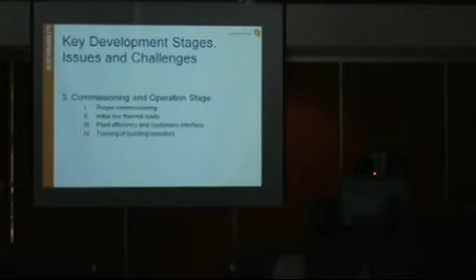So we initially suffered from a low thermal load, because we invested ahead of time. We put in too much boiler and chiller capacity, but the occupants moving in were much slower than we expected. So plant efficiency suffered, and we also needed to bring the customer in so they could understand how the system works, and most importantly, train building operators to understand how the system works.